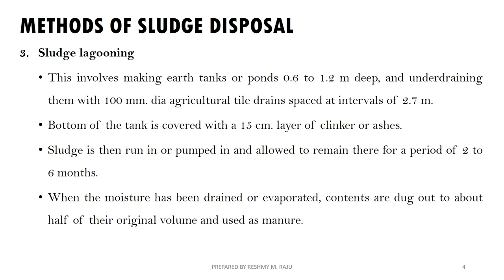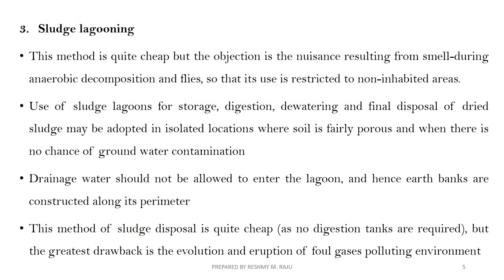We have earthen tanks of 0.6 to 1.2m deep with an under-draining system of 100mm diameter. We provide drains at intervals of 2.7m. The bottom layer consists of clinkers and ashes to form a filter layer. We pump the sludge in, and after 2 to 6 months the sludge reduces to about half its original volume.